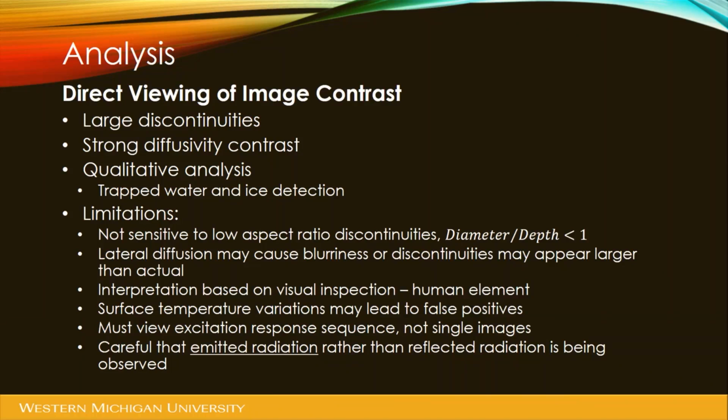So make sure you don't have a lot of heat. Even something that doesn't reflect a lot of heat is still going to have some reflection. That's a perfect one for emissivity. If you have warm objects nearby, that can throw it off. If you're imaging something right here and you've got your cup of coffee sitting next to it, that can reflect off that surface.